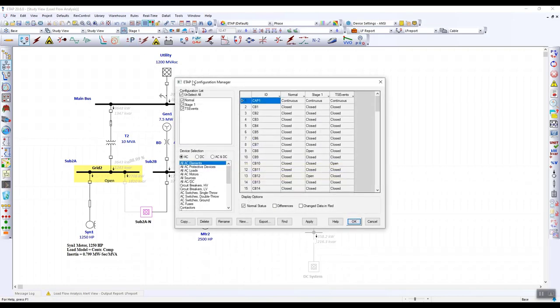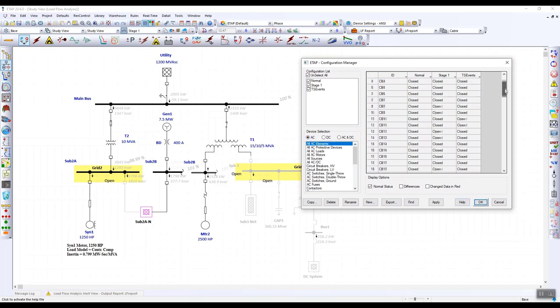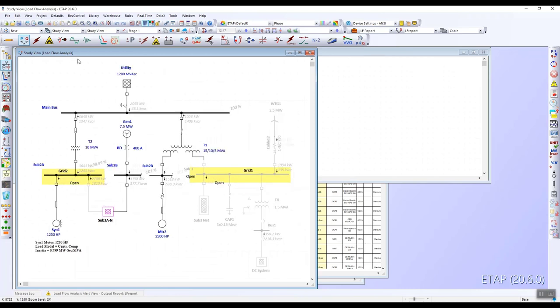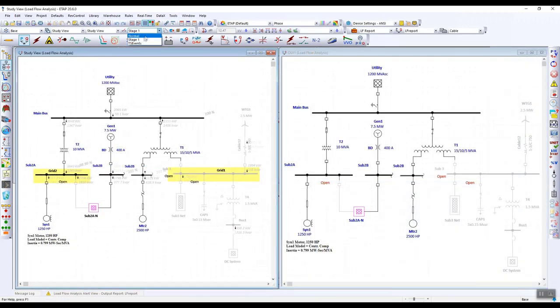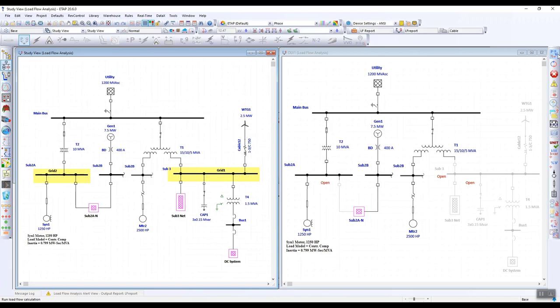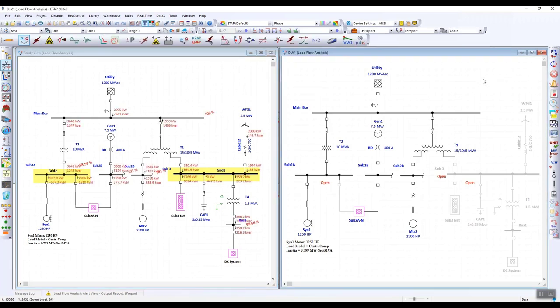We can edit all of our configurations using the configuration manager. We'll have all of our preset configurations showing and also the different statuses for our devices. We can also create a copy of the same single line diagram within the same project by creating a new presentation. On the left hand side, we're going to set the breaker statuses back to normal. On the right hand side, we're going to keep that breaker open. So what we can do is rerun the load flow study and compare the output power flow results side by side. We also have other presentations within this project.